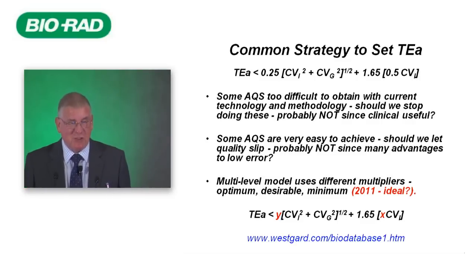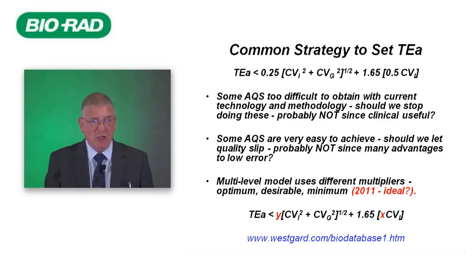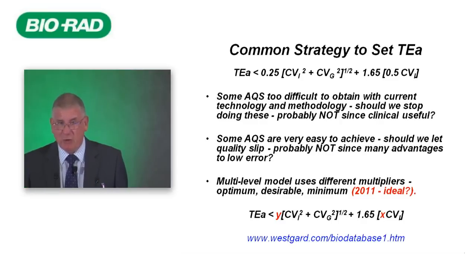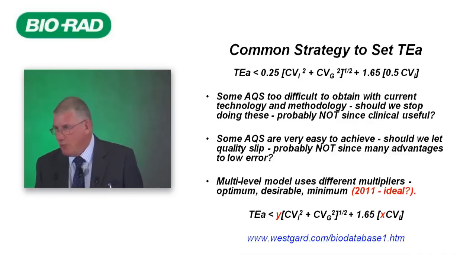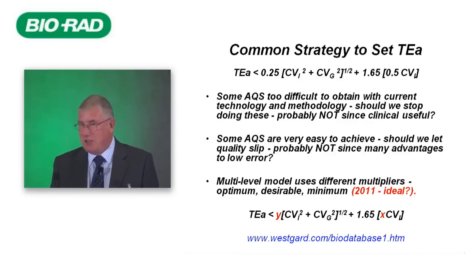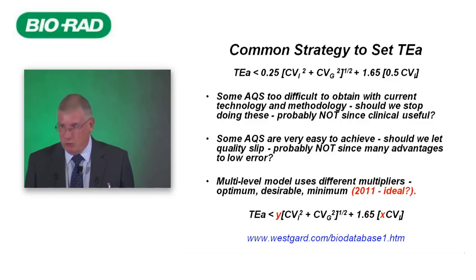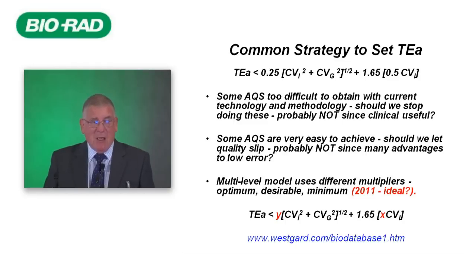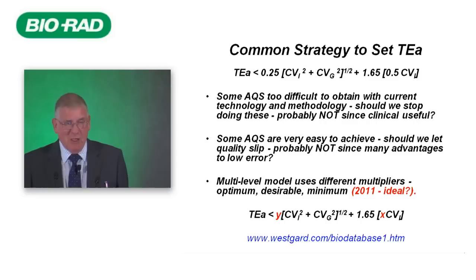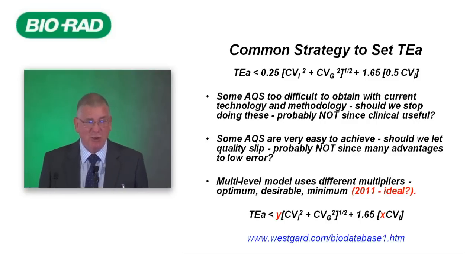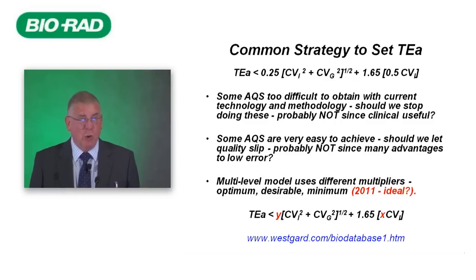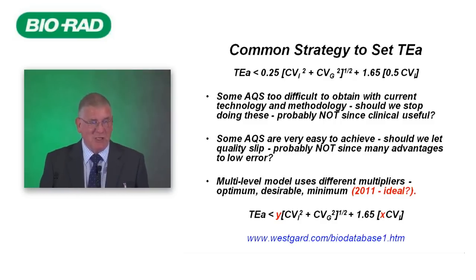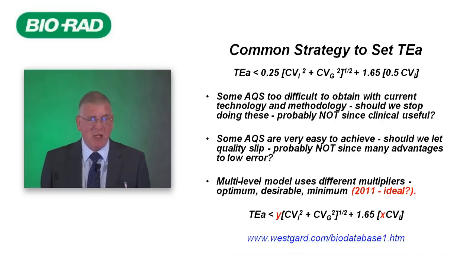If we use this formula, some quality specifications generated are very difficult to obtain with current technology — for example, for sodium, chloride, and calcium. Should we stop doing these tests because they don't meet analytical quality specifications based on biological variation? No, because we do get clinically useful data. Conversely, some quality specifications, for example for triglycerides or enzyme activities, are very easy to achieve. Should we let quality slip? Again no, since there are many advantages to having error or uncertainty lower than the analytical quality specification. Of course, we can have multi-levels using different multipliers: optimum, desirable, minimum.